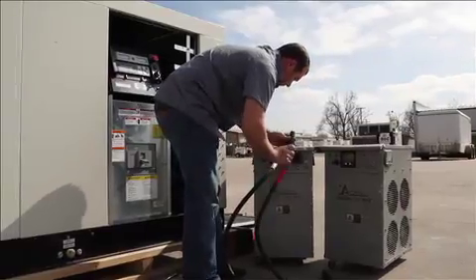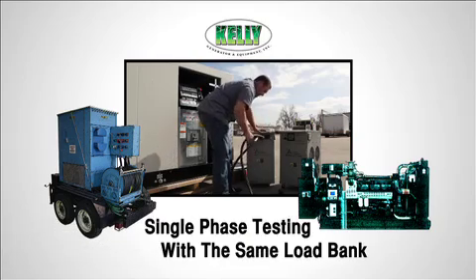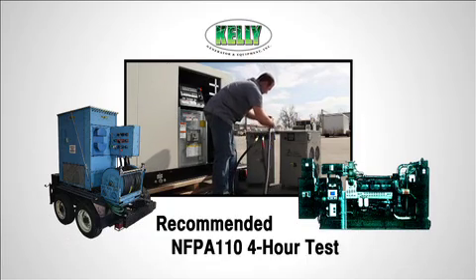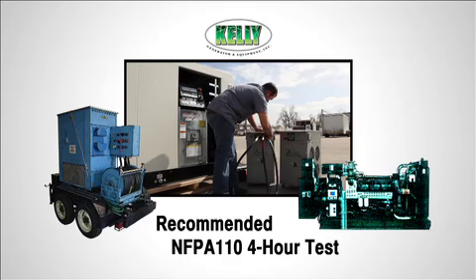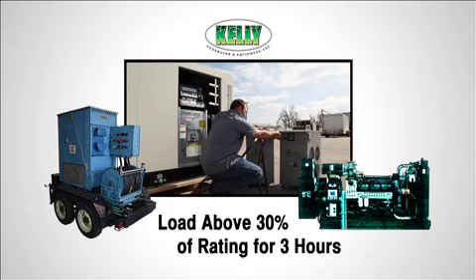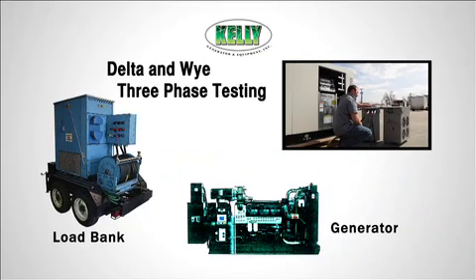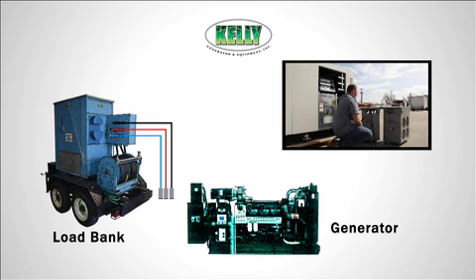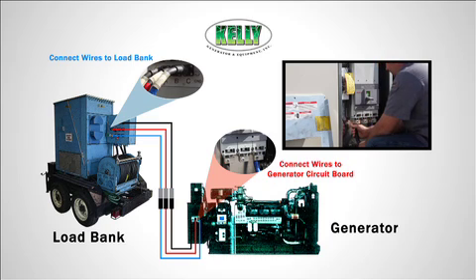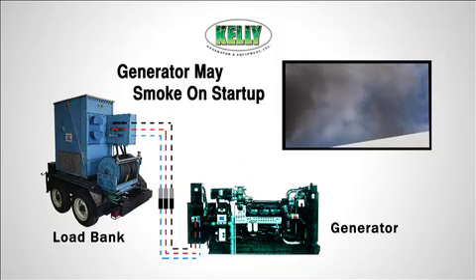Load banking can be part of the usual planned maintenance contract. An experienced technician brings to the generator set a mobile load bank rated to carry the required load. Our technician carries out the recommended NFPA 110 four-hour test, which calls for a load of at least 30% above rating for three hours and above 70% rating for an additional hour. After verifying suitability for the load banking procedure, the technician first connects the wires to the load bank, then connects the wires to the generator circuit breaker. The generator set is then started, and quite often a set that has not been loaded on prior runs will smoke on start.